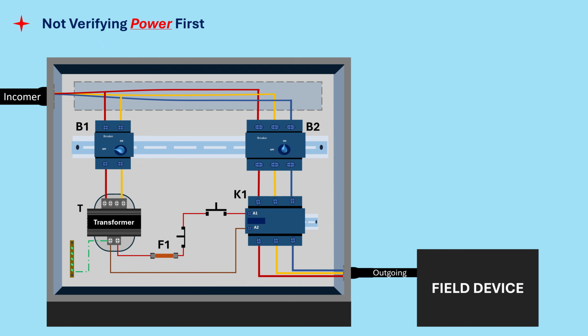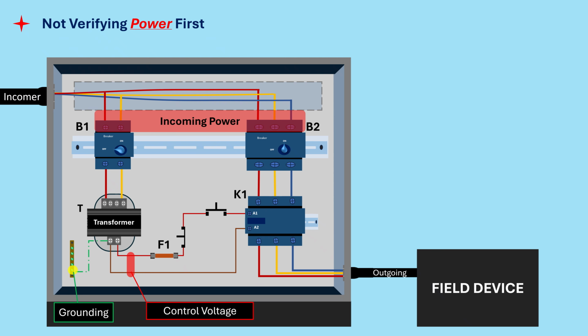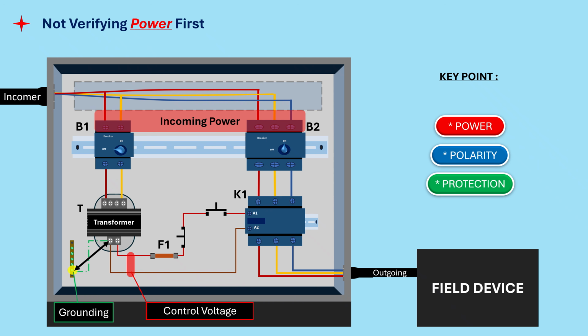Mistake number 1. Not verifying power first. Before troubleshooting sensors, PLCs, or outputs, always verify the basics, such as incoming power, control voltage, and grounding. A common mistake many technicians make is skipping the basics. Always confirm the equipment actually has power before moving on to deeper troubleshooting. The key point of mistake number 1 is to start every troubleshooting session with checking for power and verifying polarity. Always make sure the secondary side of a transformer is grounded.